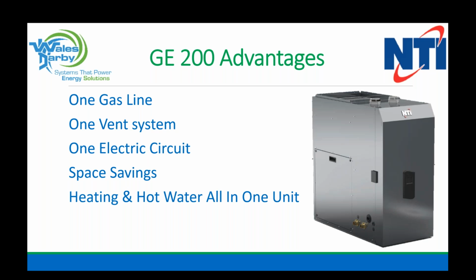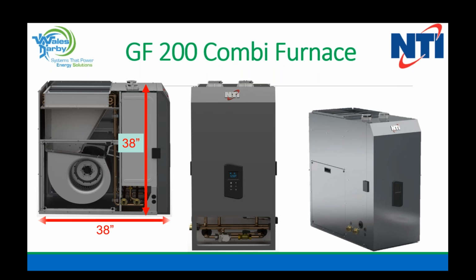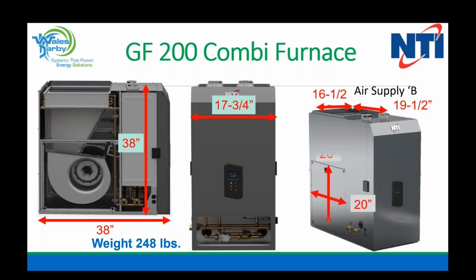Yes, it is a variable speed condensing unit, and we'll dive into that deeper. So the overall size, it's 38 inches tall, 38 inches wide, or long, I should say, 17 3/4 inches wide. It weighs about 248 pounds. You've got a B box takeoff for the supply. So if you're putting an AC coil on the top, it'll be a B style. And then on the left side and the right side, you have a 20 by 20 return air grill that cuts into the door. It can also be back or bottom for your return air.